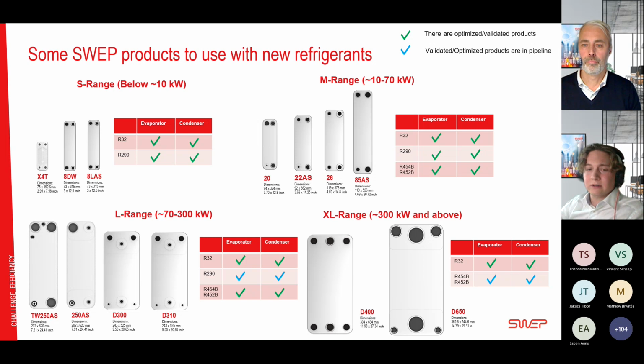And since we're talking about refrigerants here, I would like to present some of the activities we have on the XL, which is done from approximately 300 to 700 kilowatts. And here I've mainly been focusing on the R134A replacement refrigerants, which is then mainly R32. And we also intend to do some tests with the 454B going forward. I can also mention that many of the products that we have here are obviously tested with other refrigerants as well, 410A, for example, and it could be others that are also tested. Yeah, and then I would like to hand the word back to Eric for a summary.